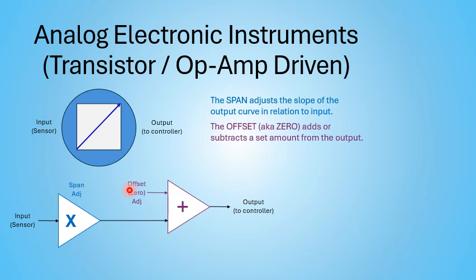I'll explain more on why the newer are better later, but to add extra circuitry, they had to add another amplifier, some kind of circuitry that would have analog electronics. They couldn't do things like compensation circuits. They couldn't add additional linearizing, for example, on thermocouple calculations. That's a pretty long polynomial equation. It's a very complex equation if you really try to get accurate. Well, they would go to about 3 layers deep and call it good enough, because there's a point where you add more electronics, you're adding more errors into the system.